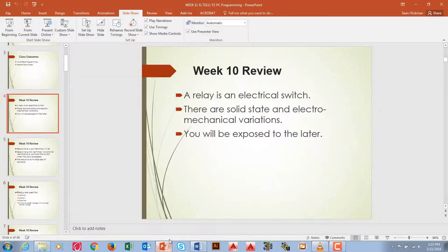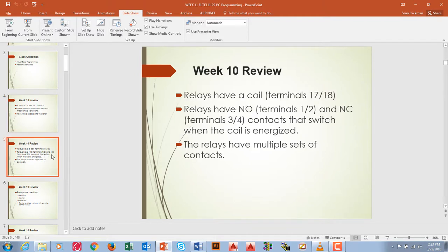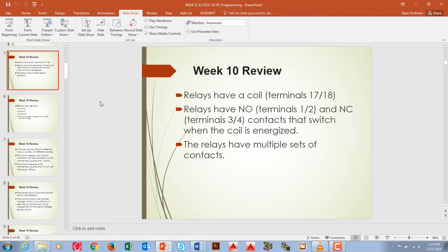There are solid-state and electromechanical variations. A solid-state relay is something like a transistor — no moving parts. That's something we'll get into a little later. The relay we covered will be in the ELTE program classes. Relays have coils at pins 17 and 18 — that's the coil, you apply power, it creates a magnetic field, and then it switches. The contacts are normally open and normally closed, and it can have multiple sets of contacts. Our relay had a bunch of different contacts, and we created some drawings with those different contacts.